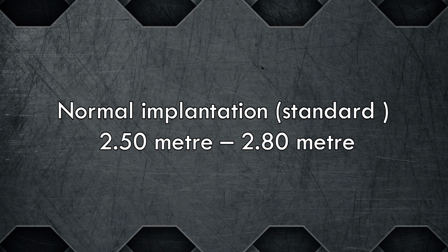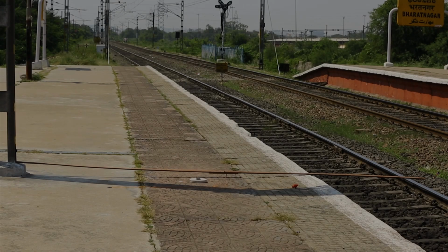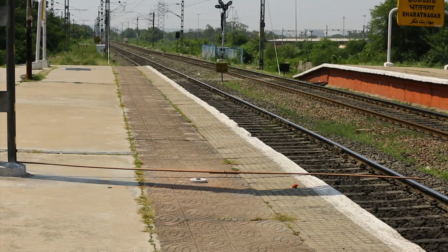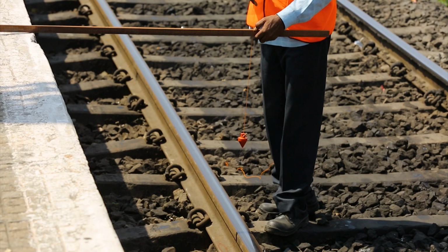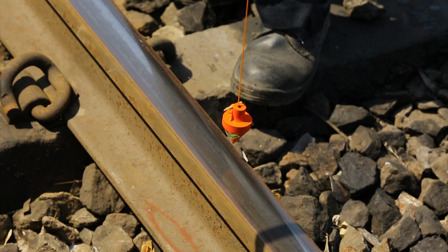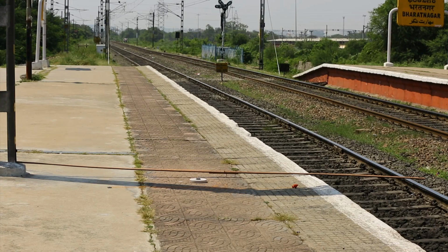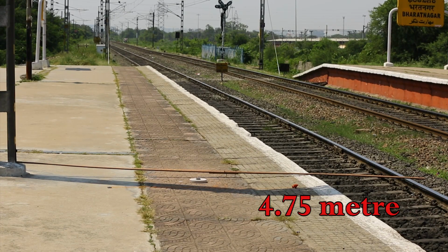Normal implantation standard: 2.5 meters to 2.80 meters. Minimum implantation in critical cases with CEE approval: 2.36 meters. To measure implantation on a platform, a plumb bob, a fiber tape, and a long stick of suitable length are used. Minimum implantation on platform: 4.75 meters.